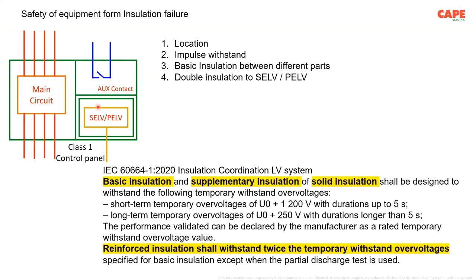Say, for example, for basic insulation coordination, standards are there, IEC 60664 part 1. I am just showing some of the part. This is applicable for equipment. Let me read it. Basic insulation and supplementary insulation of solid insulation shall be designed to withstand the following temporary withstand overvoltages.